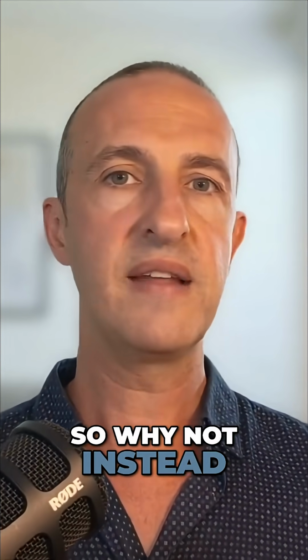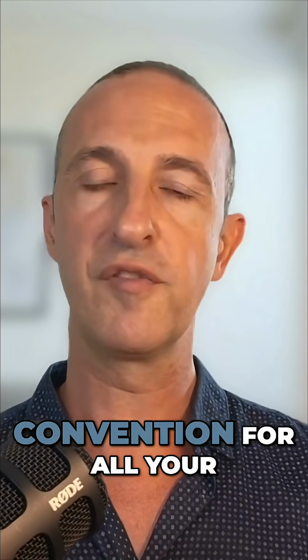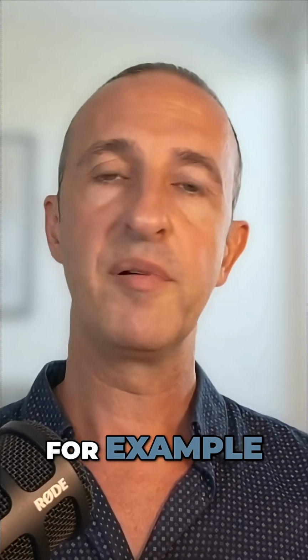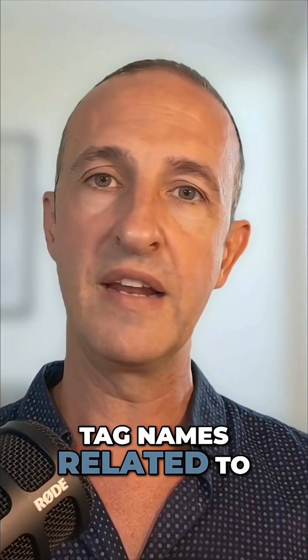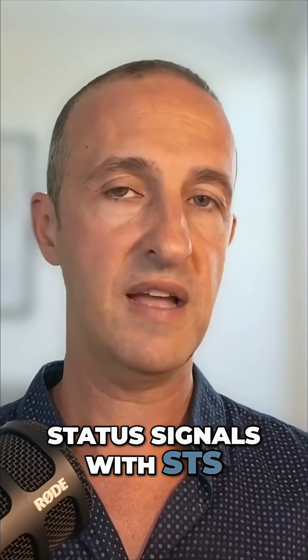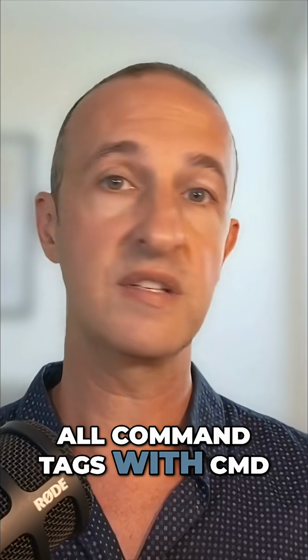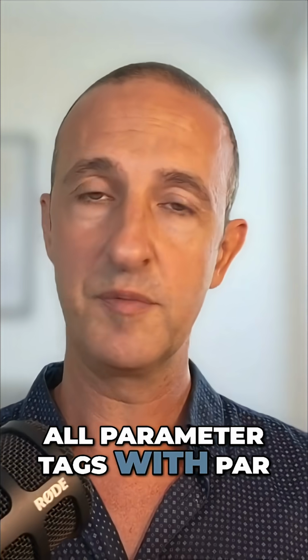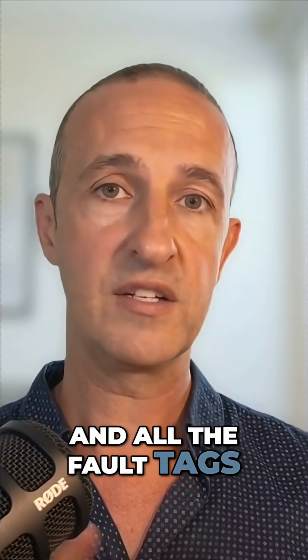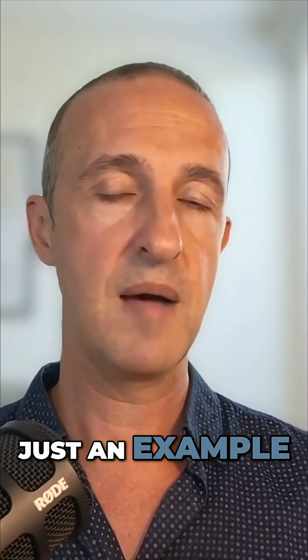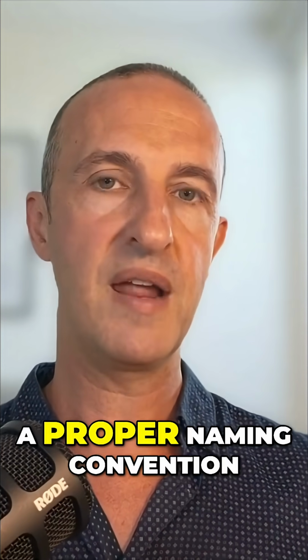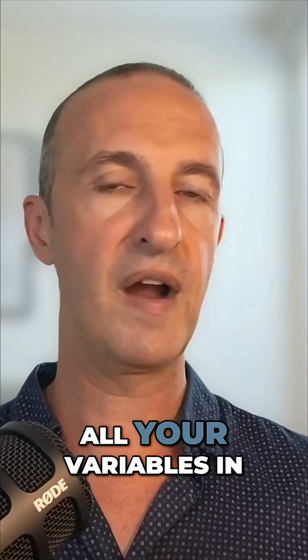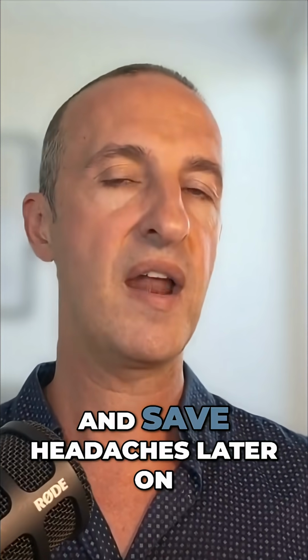So why not instead adopt a standard naming convention for all your tags in your project? For example, you can start all tag names related to status signals with STS, all command tags with CMD, all parameter tags with PAR, and all fault tags with FLT. Just an example. So start by defining a proper naming convention for all your tags, all your variables in your project, and save headaches later on.